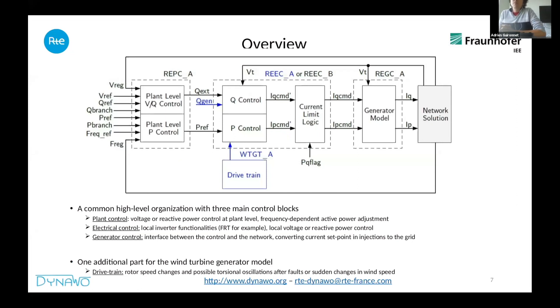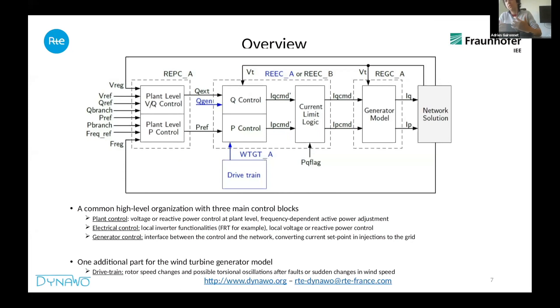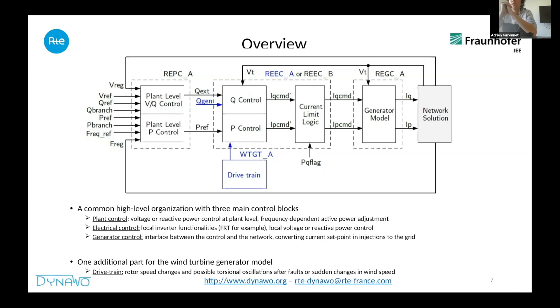Looking at the model in a general view, there are basically three layers: the plant-level control, which manages the voltage and active power control at plant level and also does frequency-dependent active power adjustment. Then from this you go towards the electrical control, where you have local inverter functionality such as local voltage or reactive power control, as well as current limit logic that gives priority to reactive or active current. Once through the electrical control, you have a reference current for active and reactive current that goes to the generator model, which converts this reference to injection into the network.